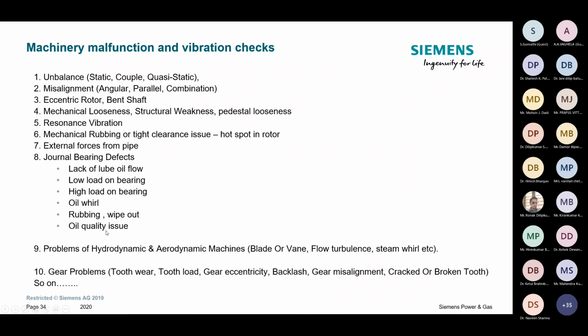On oil quality, the oil normally heats up due to friction, and the exhaust temperature of the oil will be in the range of 80 to 90 degrees Celsius, and they need to cool it to 40-43 degrees Celsius. So it passes through the cooler. Now many times coolers get punctured, oil and water get mixed up, and the required viscosity gets reduced, and you will not get the desired parameters. So that is also possible.